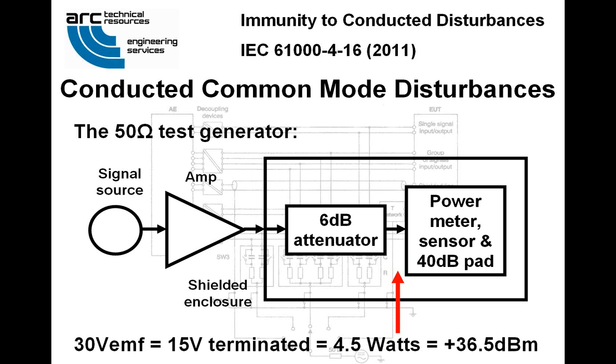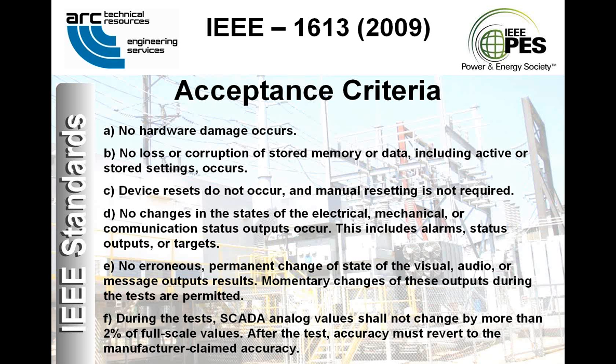No hardware damage, of course. No loss or corruption of stored memory or data, including the settings. The thing does not reset. Manual resetting is not required. The changes in the states of electrical, mechanical, or comm outputs are not supposed to occur, like alarms. No erroneous permanent change of the visual front panel of the thing. Momentary is okay. And the analog values shouldn't change by more than a couple of % full scale and have to revert later without intervention to the manufacturer claimed accuracy.